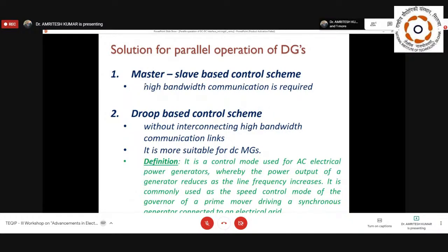So without interconnection, no high bandwidth communication is required. It is more suitable for the DC microgrid. I have taken one definition from Wikipedia. This is droop-based control. As we know, for our conventional utility, it is a control mode used for AC electrical power generators, whereby the power output of a generator reduces as the line frequency increases. So basically, we were using this droop scheme in the normal grid system, where a number of synchronous generators are connected in parallel, and without any communication they are able to share the power. And that is based on the droop only.